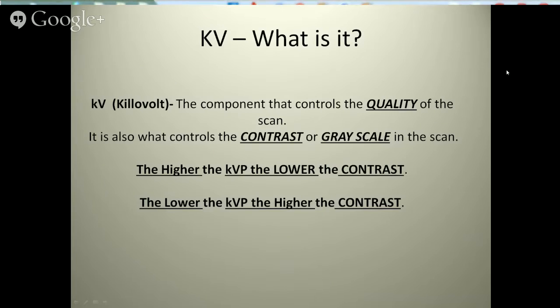I'm going to go into a little bit about if you're not getting good scans, what could be the problem. So KV, what is KV? It's kilovolts, and that part of your controls takes care of the quality of the scan. It's what controls the contrast or grayscale in the scan.